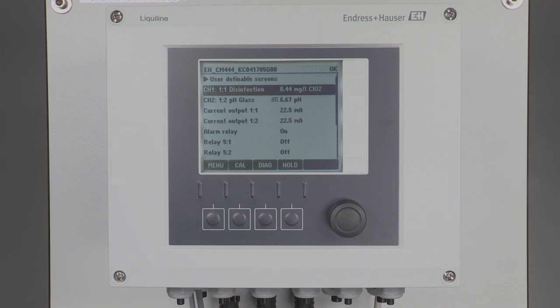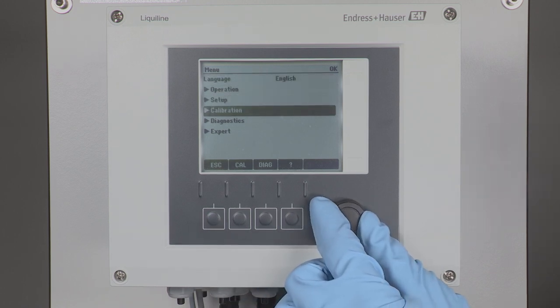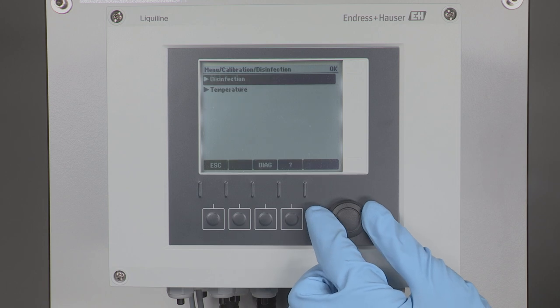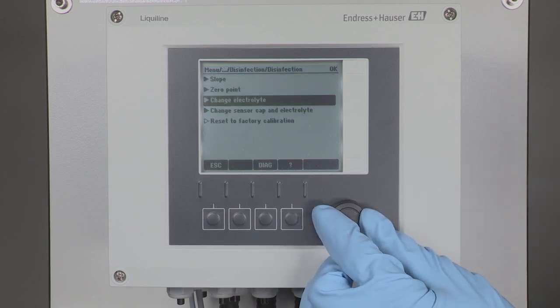Reset the operating hours counter for membrane and electrolyte in the Liquiline CM44 transmitter. Go to menu, calibration, the channel of your chlorine dioxide sensor, disinfection, and change sensor cap and electrolyte.